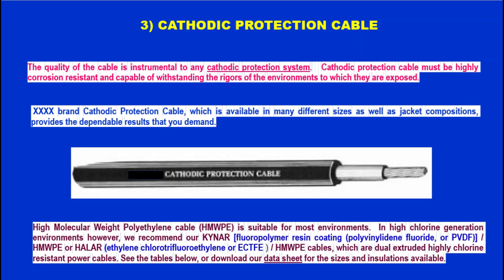High molecular weight polyethylene cable is suitable for most environments. In high chlorine generation environments, the recommended cable is KYNAR fluoropolymer resin coating — polyvinylidene fluoride (PVDF). Other options include high molecular weight polyethylene or halar ethylene chlorotrifluoroethylene (ECTFE), and dual extruded, highly chlorine resistant power cables. Refer to data sheets for the sizes and insulations available.